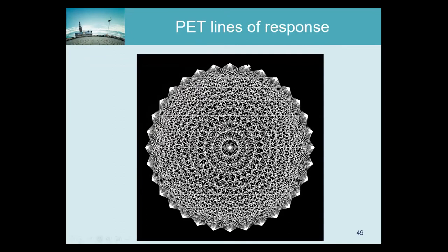If you do quality control in a PET camera using a point source, you can have very weird effects because a point source reveals this kind of sensitivity variation. Placing a point source at strategic positions means the PET will see more photons than at other places. As soon as the object is a bit larger — a small sphere, for example — those effects disappear. But a point source or line source placed exactly in the center of the scanner will have extremely high system sensitivity.